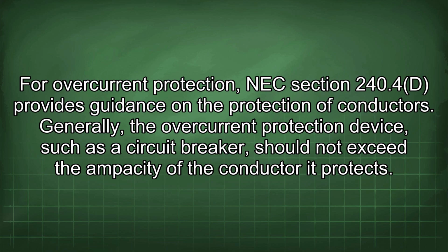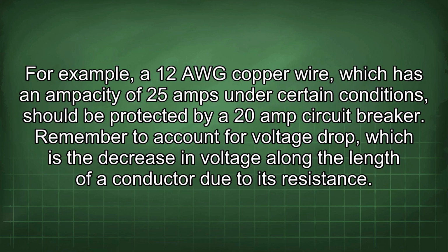For overcurrent protection, NEC Section 240.4(D) provides guidance on the protection of conductors. Generally, the overcurrent protection device, such as a circuit breaker, should not exceed the ampacity of the conductor it protects. For example, a 12 AWG copper wire, which has an ampacity of 25 amps under certain conditions, should be protected by a 20 amp circuit breaker.